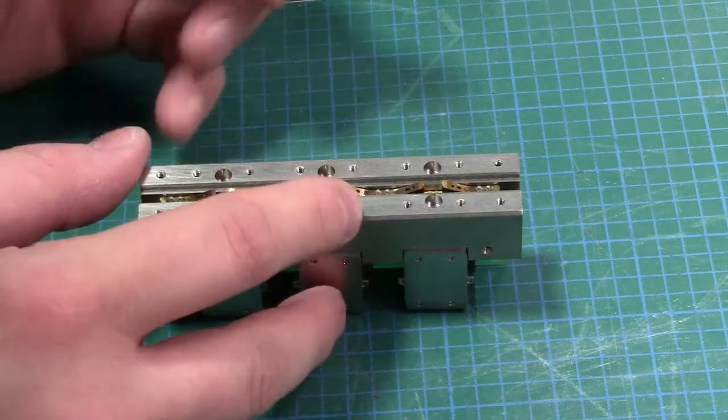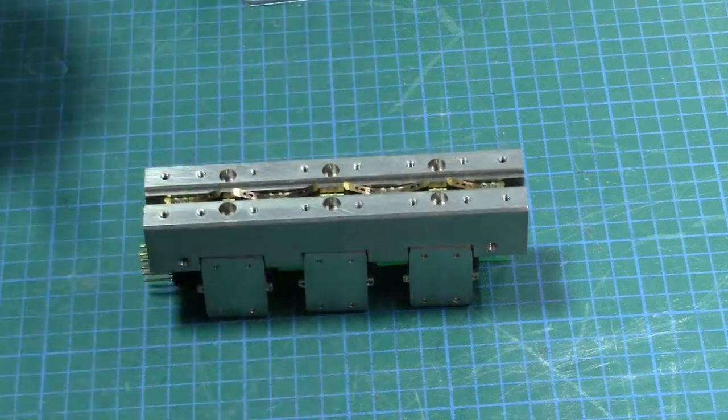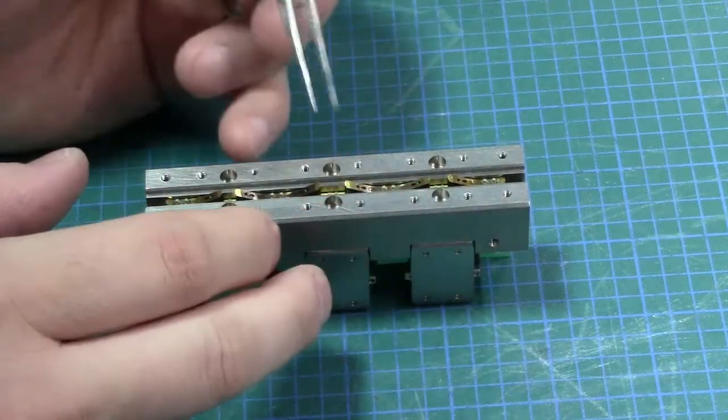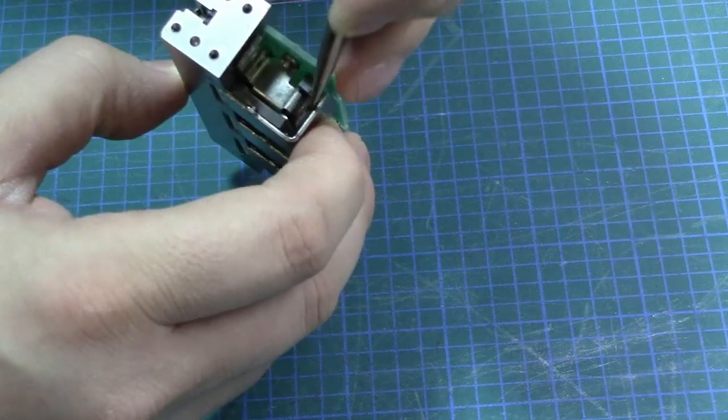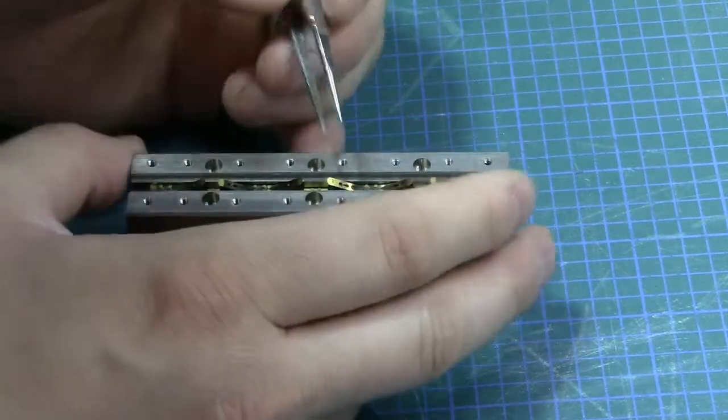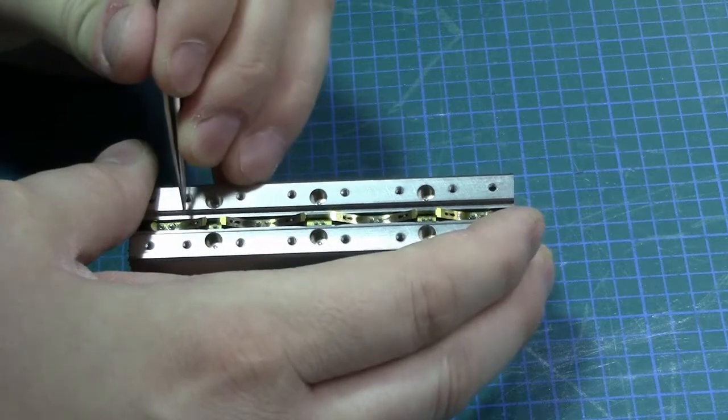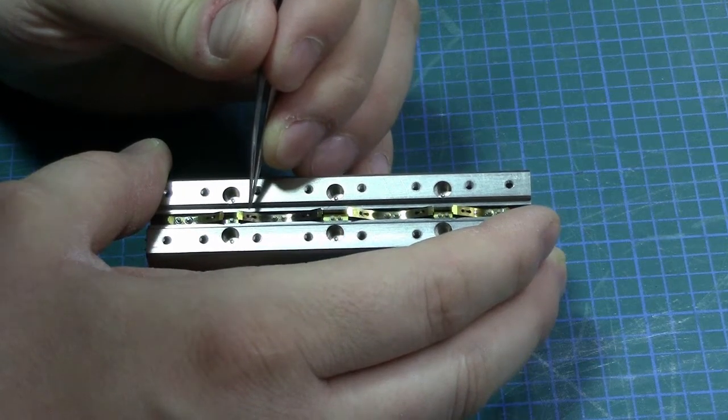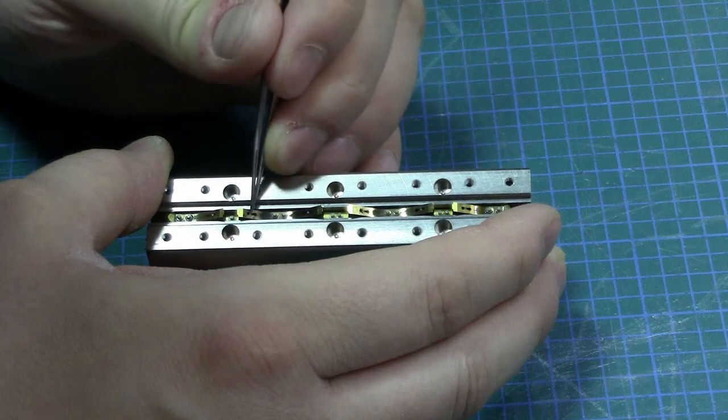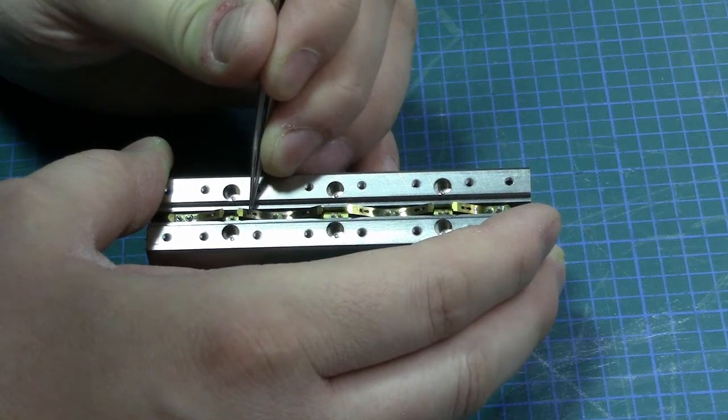I've reassembled the two modules. The pistons are now poking up through the holes against the actual actuator contacts. And the thing to remember here is that when you put them together, the actual pistons behind here, which are part of the actual relays, they need to be pushed all the way towards the attenuator block. And the reason for this is if you don't, you're not going to put enough tension and the pistons won't be in the right place. You won't be able to attach them correctly here. So I'm going to try and do this.